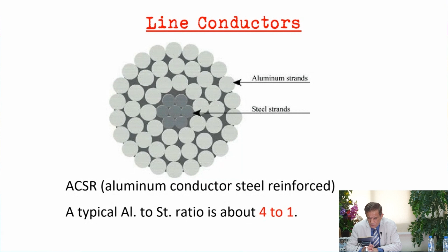We have for these conductors a unit which is always used. You have to be familiar with this unit, which is the circular mil. The circular mil is the area of a conductor having a diameter of 1 mil. A mil is 1 over 1,000 of an inch. A thousandth of an inch is the mil. If I bring a wire with a diameter of 1 mil, then it will have an area of 1 circular mil. Its actual area is, as you know, pi r squared. So you multiply pi by r, which is d over 2, that is 0.001 over 2, which is 0.0005 squared, by pi. This is the actual area.